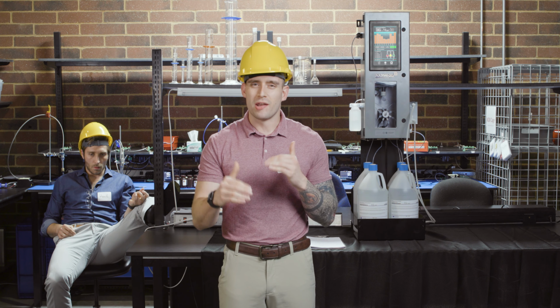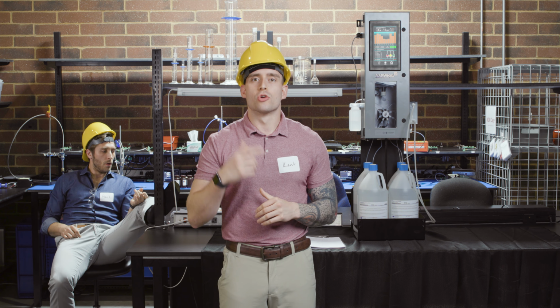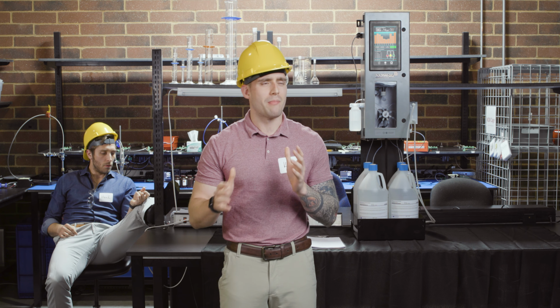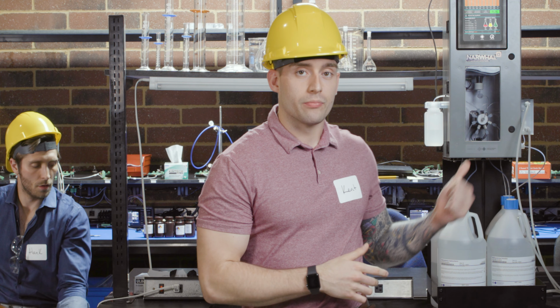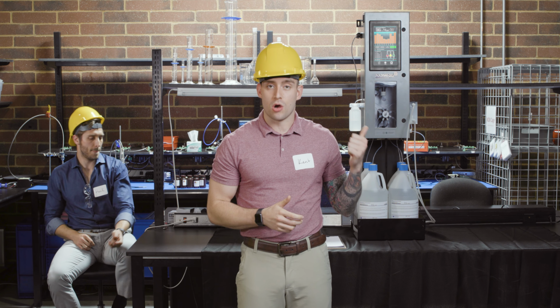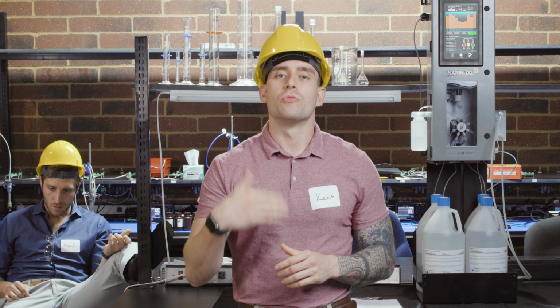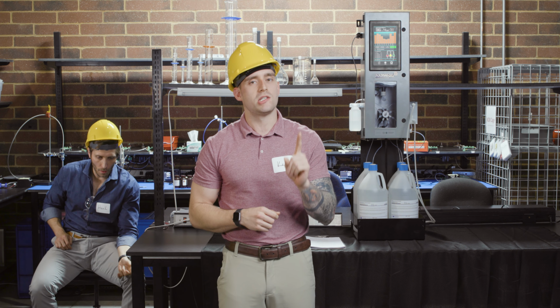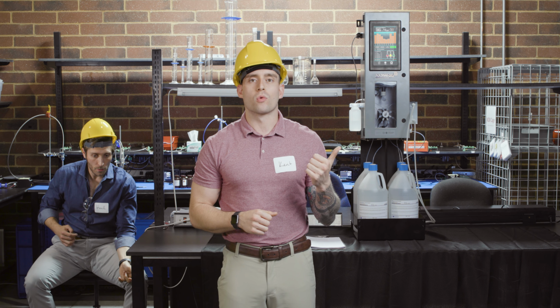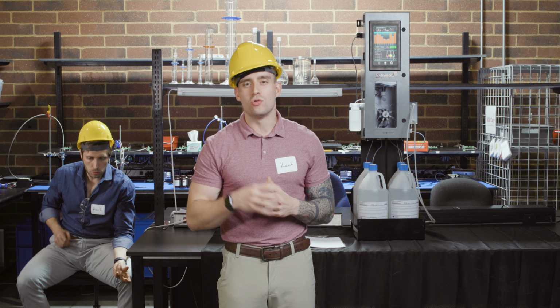There are gonna be a couple of things that we're gonna have to replace when it comes to maintenance. Depending on your frequency of measurements, your reagents should be swapped out about every 3 months. With the Narwhal, there's actually gonna be 2 things that you replace on the machine itself. First, you're gonna wanna replace your piston seal at least once per year. Then, you're gonna wanna replace the tubing once every 2 years or so.